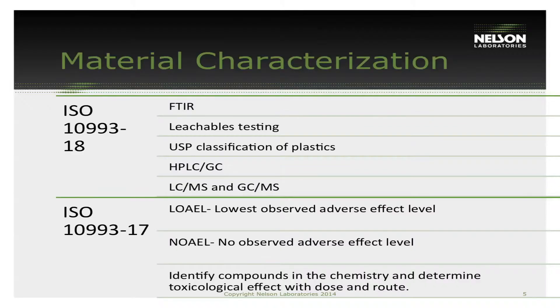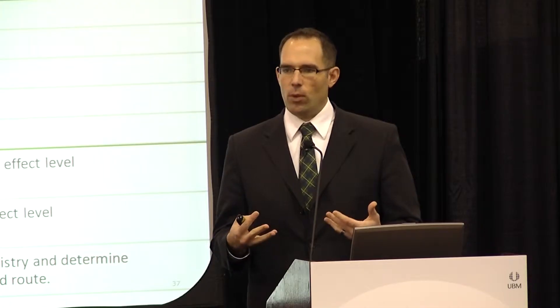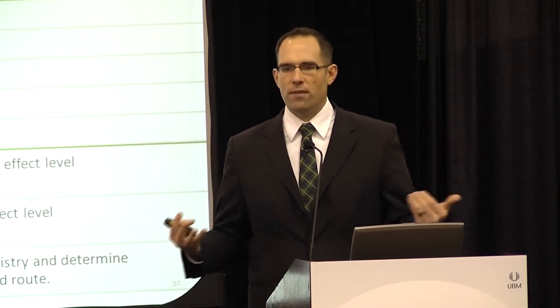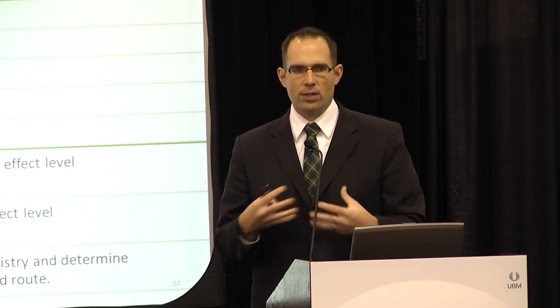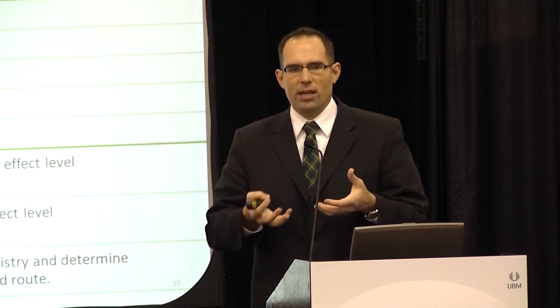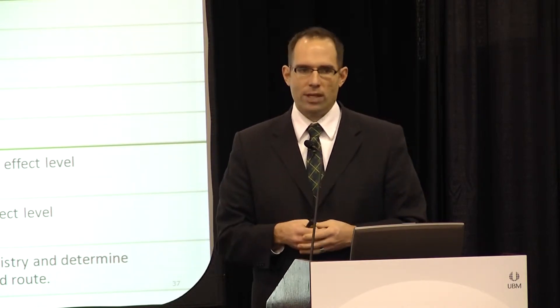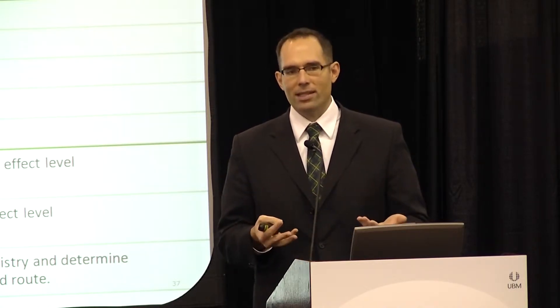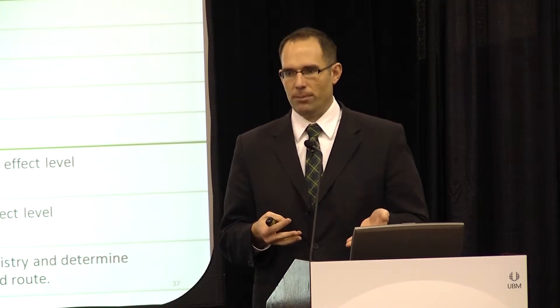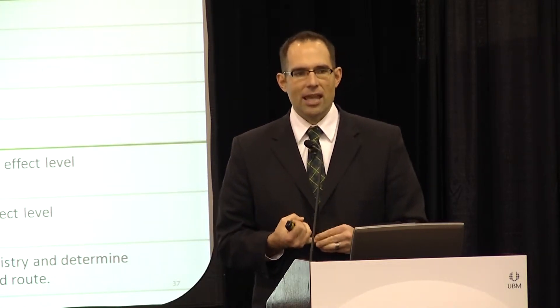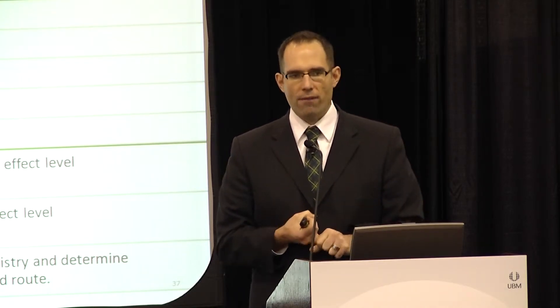ISO 10993-18 gives you a list of chemistry techniques we can use to help identify what those compounds are. When you look at a leachable/extractable program, we extract the device — put it in some kind of liquid at some temperature and time — and pull off those compounds, leaving us with a solution of chemistry off your device. The next step, and probably one of the hardest, is to identify and quantify what those compounds are.